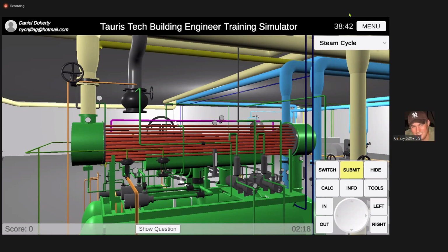No, you see this line right here that I'm pointing to? Vapor. Right, that's your vapor line, your vapor header. That vapor header goes to your vacuum pumps. That's pulling the vapor, non-condensables, out of the surface condenser, and it's pulling it down to vacuum pump 1 and vacuum pump 2. So we're going to hide that line right there. Okay? And then you got this from the vapor header to vacuum pump 1. There's another one here. Vacuum pump 2. Okay?